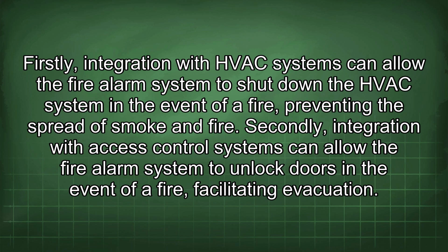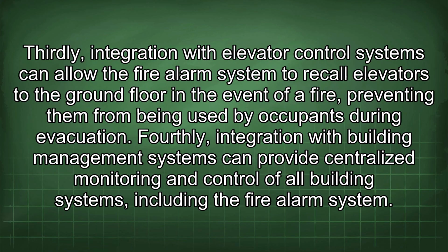Secondly, integration with access control systems can allow the fire alarm system to unlock doors in the event of a fire, facilitating evacuation. Thirdly, integration with elevator control systems can allow the fire alarm system to recall elevators to the ground floor in the event of a fire, preventing them from being used by occupants during evacuation.